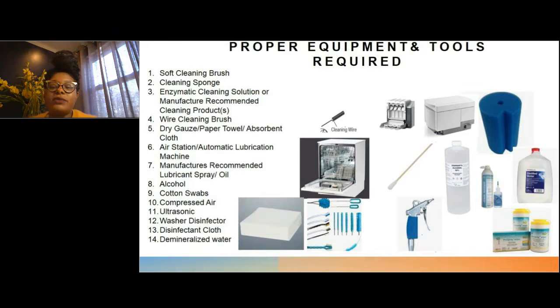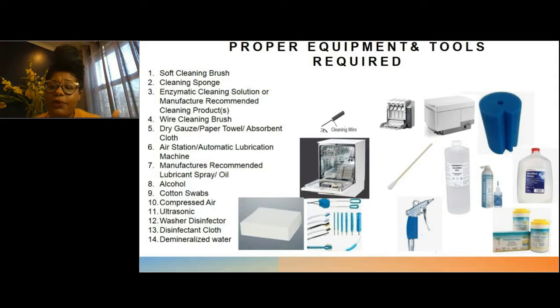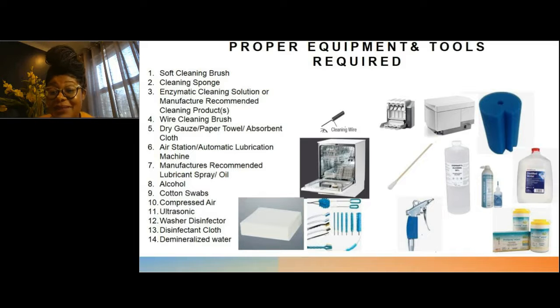So what I did when I was going through different IFUs for different hand pieces, I counted 14 tools or equipment that the IFUs are saying are needed in order to properly reprocess these hand pieces. And this is before we're even talking about the PPE that needs to be worn by the staff who is reprocessing them, and that's considered equipment too. So it's very important that you're taking the time to dissect your IFU and make lists of exactly what's needed in order to do the reprocessing correctly.